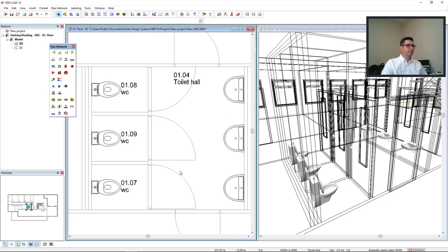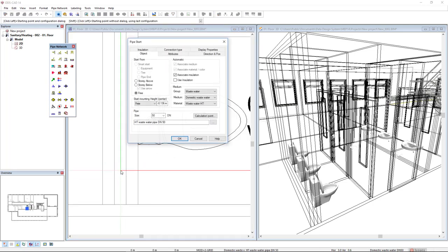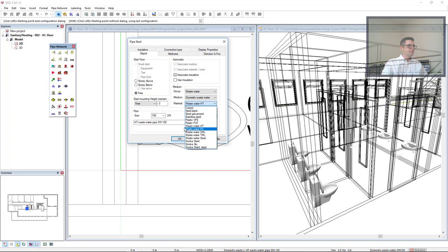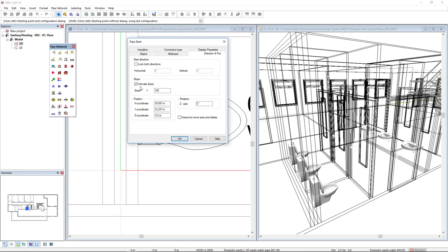Now I would like to insert pipe behind the objects. I start the pipe function and define the pipe start. I will change the pipe size to 100 and change the mounting height to minus 0.2. Here we see we already have the correct group, medium, and material. The material indicating wastewater allows us to activate the slope. In the tab Direction, we see the slope is already active, and here we see the angle of the slope. If I insert minus, by default the pipe will come down. Click OK.